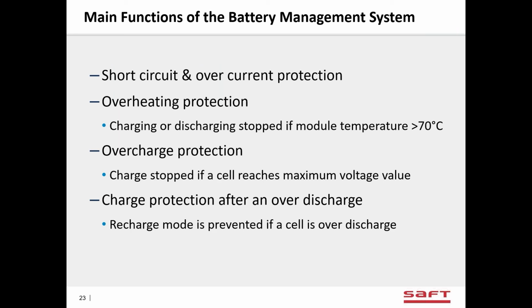You have to protect against short circuits and overcurrents, overheating. So if we get to 70 degrees C, we're going to disconnect that battery so that it doesn't go hot enough to go into thermal runaway. So you have to design the battery room so that it's best to have the battery room be a temperature controlled space for lithium-ion batteries.